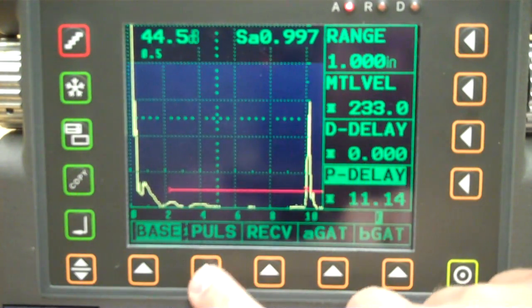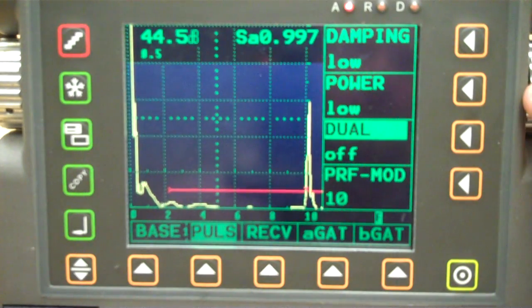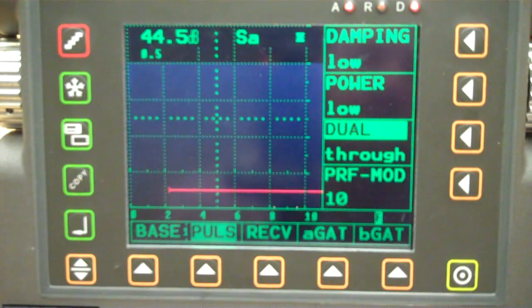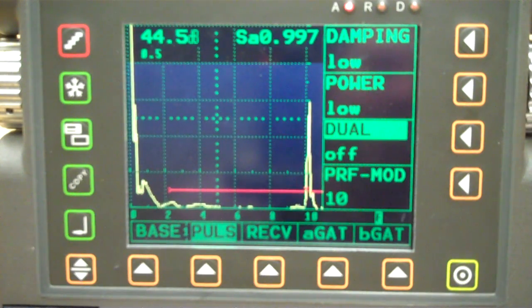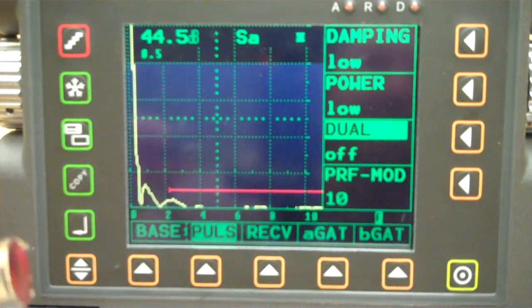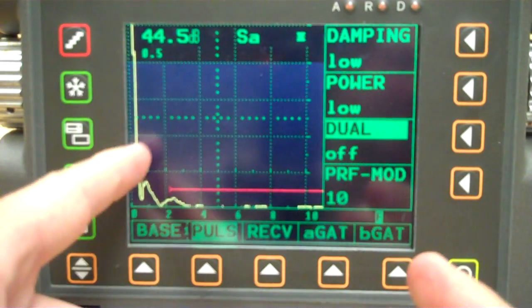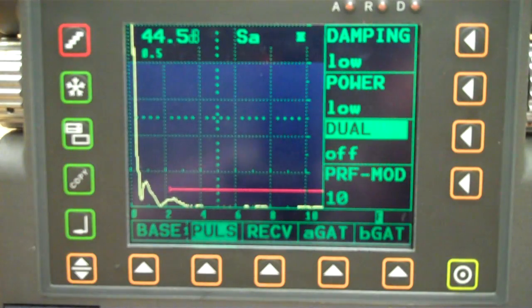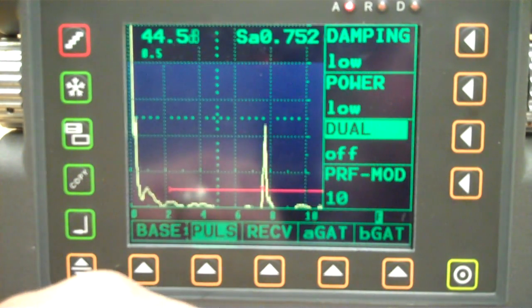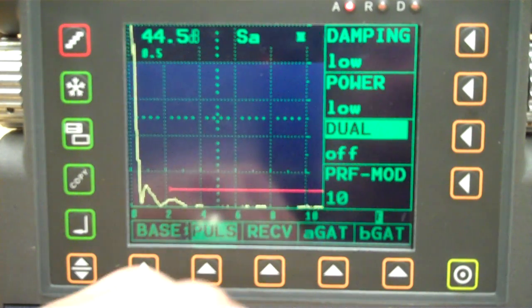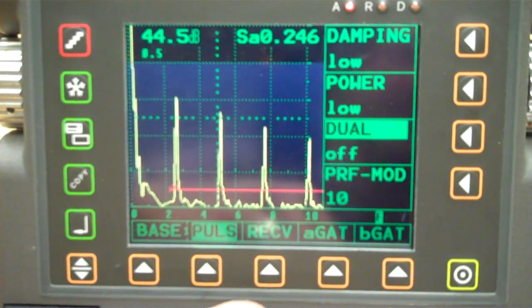So if we go back to our pulser and just look at that dual element one more time, something completely different happened, or we lost our signal, because we only have a single element transducer. And the single element is trying to talk to the second element, which is not there, so you can't get anything through it. So anyway, turn that off. Dual element right there. If we hit the end of this, you see this signal right here dampen down, and that's a good thing. That means we're right at the edge. Then we're 1 inch, 3/4, half, 1/4 of an inch. Just like that, easy money.